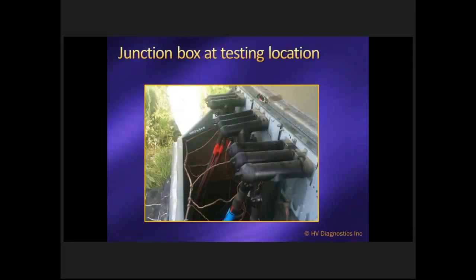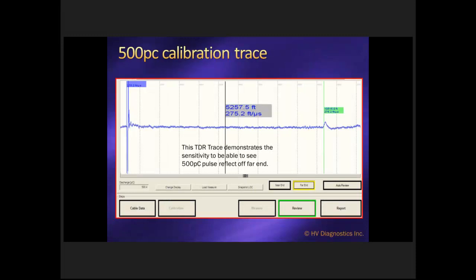If you look at the typical situation, those of you who've done testing on wind farms are familiar with the typical T-body installation. And we look now at the calibration pulse that we inject artificially into the cables to calibrate our system. You can see over there a very nice reflection from the far end, and bear in mind this is 10,000 feet of cable, which is a very long length of cable. So clearly we see attenuation of the impulse. This big impulse has been reduced to that, but you can clearly see the end of the cable. That's a 500 picocoulomb pulse.